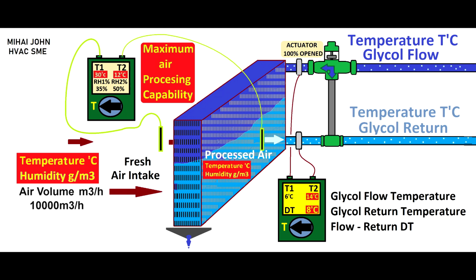It is evident from the provided information that the AHU is inadequately designed to withstand outdoor temperature conditions. The air handling unit is unable to effectively process the incoming outdoor air at elevated temperatures, thus failing to attain the desired set point. A critical aspect in this situation is the adherence to the AHU's design specification. It has been observed that many engineers might not thoroughly review the AHU specification, which ultimately results in their inability to address this issue effectively. Consequently, they face scrutiny for their perceived incapacity to manage the situation adequately.